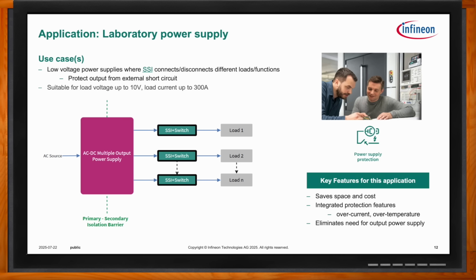The system can handle up to 10 volts at 300 amps while protecting against external short circuits. That's impressive because it shows just how scalable our solid state isolator is, supporting low voltage but extremely high current scenarios. Another plus is that SSI eliminates the need for a separate output power supply, which saves space and simplifies design. For labs, this translates into power supplies that are safer, more compact, and capable of handling extreme current loads without relying on bulky, failure prone mechanical relays.